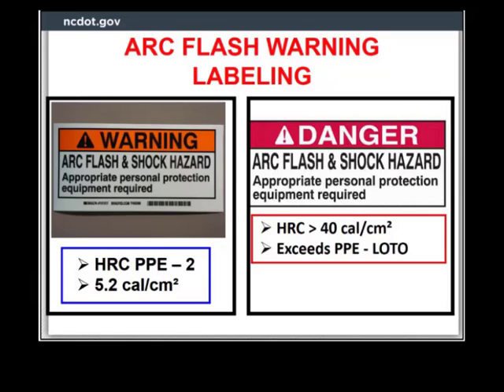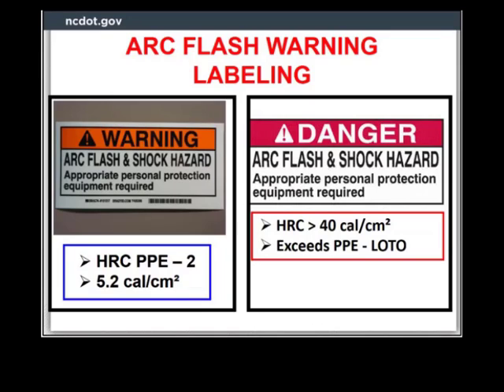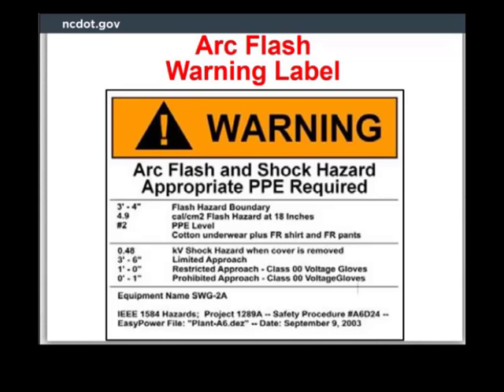Most 120-208 electrical panels do not have sufficient energy for a sustained arc to be maintained and will not be labeled. Labeling applies primarily to 480 volt or greater electrical panels. This label meets the 2015 version of NFPA 70E. The following information must be included on arc flash warning labels. Arc flash boundary, at least one of the following. Available incident energy at the corresponding distance. Arc flash PPE category. Minimum arc rating of clothing or site-specific level of PPE.